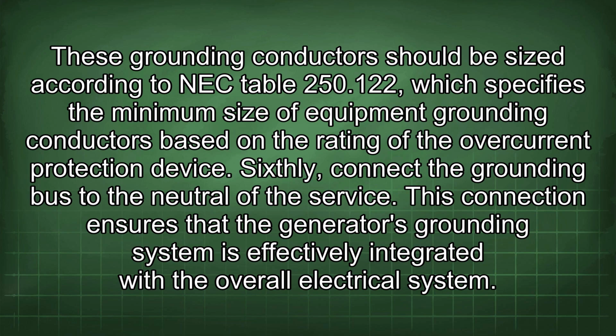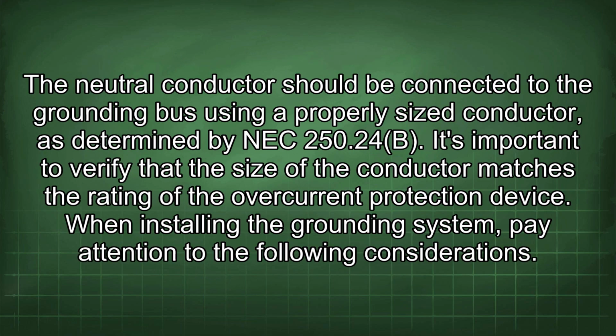Sixthly, connect the grounding bus to the neutral of the service. This connection ensures that the generator's grounding system is effectively integrated with the overall electrical system. The neutral conductor should be connected to the grounding bus using a properly sized conductor, as determined by NEC 250.24(B). It's important to verify that the size of the conductor matches the rating of the overcurrent protection device.